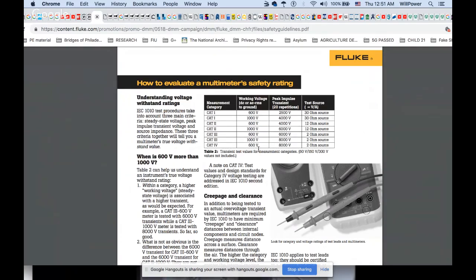So what happens when an explosion happens in here, it's going to try to short it out and keep it inside this compartment, where in theory, I have not been able to find testing on that. I would love to find it. The leads are now going to be able to take the higher voltage. We're only talking 600 volts here on the Category 4.